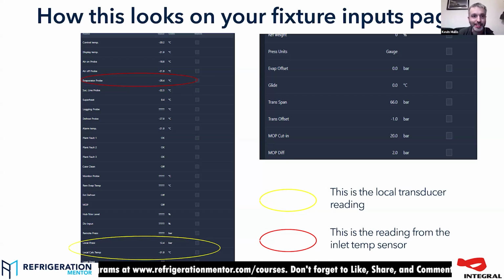It's really difficult to mount it to like a 1/4-inch distributor leg. And a lot of your evaporator manufacturers used to give you a little bit of pipe after the distributor, before it went into the coil. Not a lot of them give you that now. They just crimp the end of the pipe down right onto the distributor, and it's really difficult to mount the probe. Now, a lot of the manuals will tell you to mount the evaporator inlet probe at the opposite end of the evaporator to where your valve's mounted.